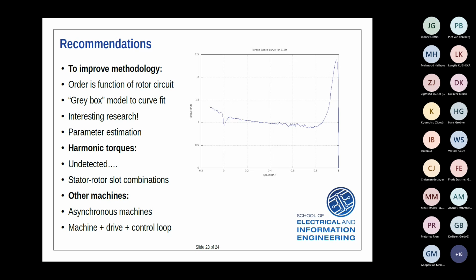So where do I see this going? If we can do some parameter estimation to estimate or measure the voltage, and measure the current, we'd know another variable, and combining that with the audiogram, we could eventually produce something that runs on a smartphone to do this on site, in location. If you could disconnect the machine, run it at a reduced voltage, measure the audio and the current, you could then produce a curve on the spot - that's what I'm suggesting, using the processing ability of these smartphones.